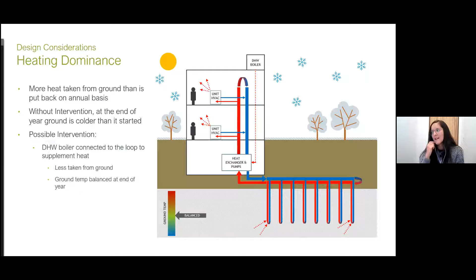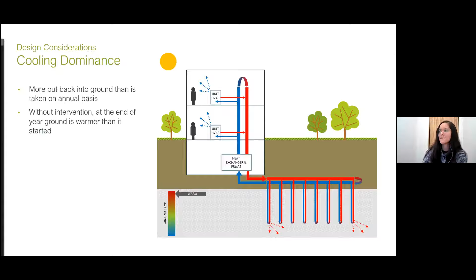On the flip side, a cooling dominant building is one that puts more heat back into the ground loop than is taken out at the end of the year, so it's cooling more than it heats. This type of imbalance in cold climates is actually a bit easier to manage, because you have an excess of heat in the ground at the end of your cooling cycle that you need to expel. So you can find ways to expel that heat, like heating your parking garages, snow melt systems, or preheating water, because you've got this abundance of heat.